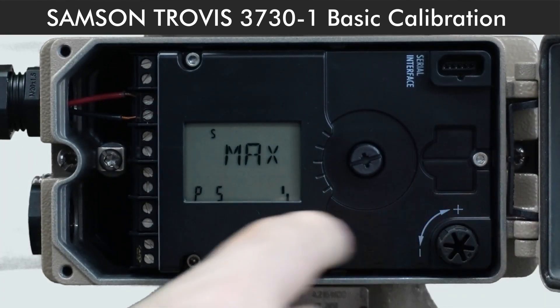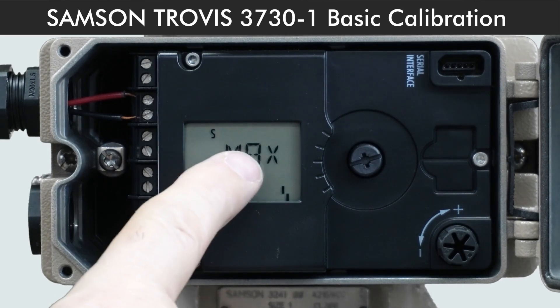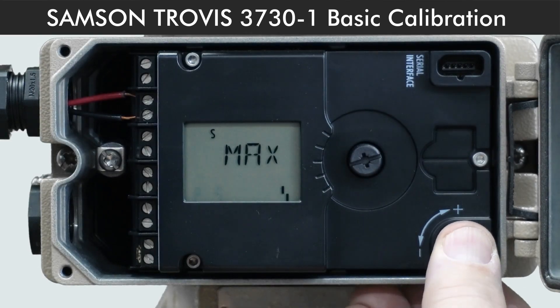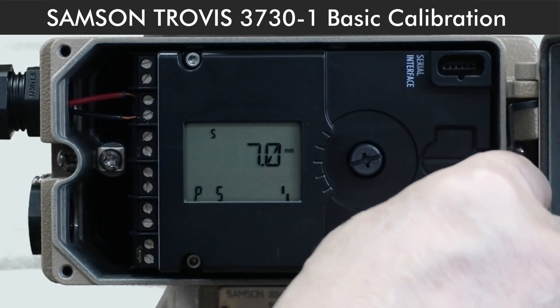P5 is for setting the nominal range — max if you want to go above 15mm. For 15mm stroke, push this button and turn the dial until you get 15mm, then push it again.